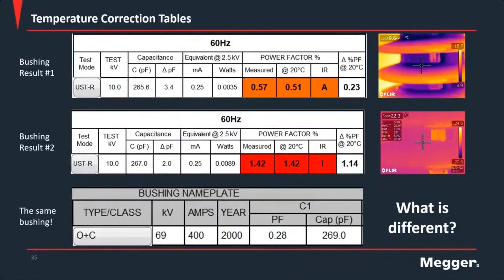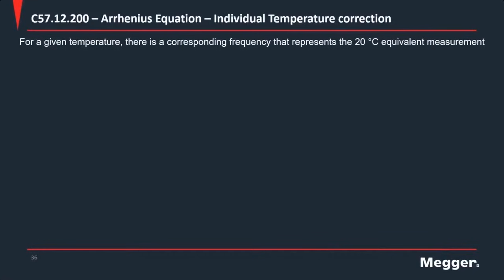So what can we do? If we know that temperature correction tables don't work when bushing insulation starts to deteriorate, is there another option for us? And that other option is called the individual temperature correction. And this comes from C57.12.200, where it is called the Arrhenius equation. And Arrhenius was a guy back in the 1800s who found out that there's a relationship between temperature and frequency.